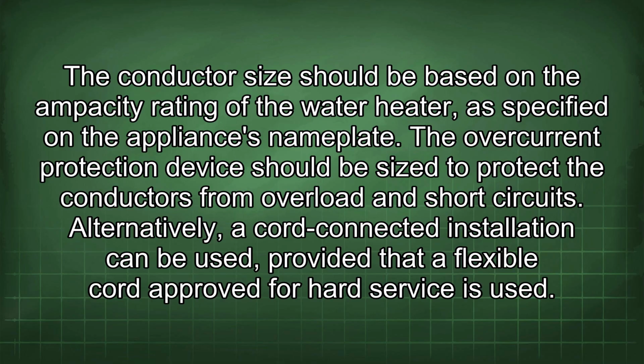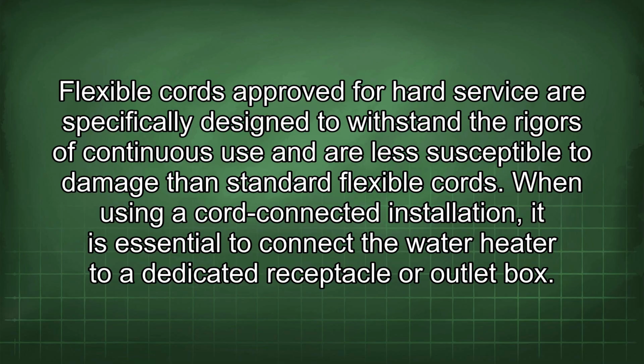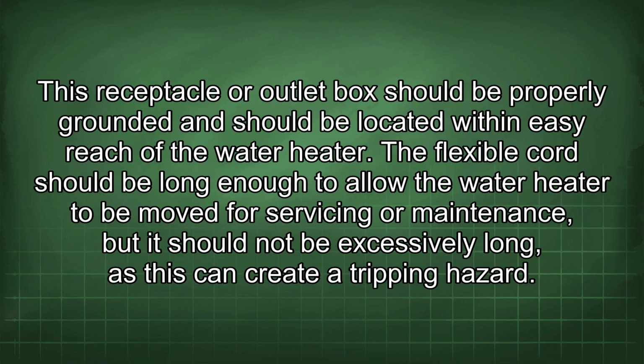Alternatively, a cord-connected installation can be used, provided that a flexible cord approved for hard service is used. Flexible cords approved for hard service are specifically designed to withstand the rigors of continuous use and are less susceptible to damage than standard flexible cords. When using a cord-connected installation, it is essential to connect the water heater to a dedicated receptacle or outlet box. This receptacle or outlet box should be properly grounded and should be located within easy reach of the water heater. The flexible cord should be long enough to allow the water heater to be moved for servicing or maintenance, but it should not be excessively long, as this can create a tripping hazard.